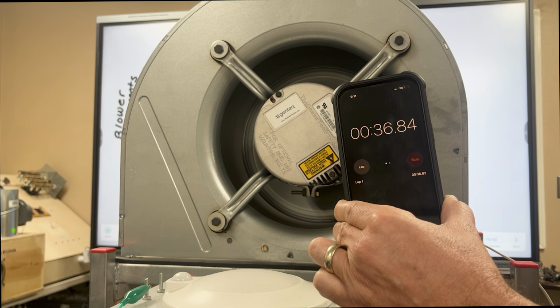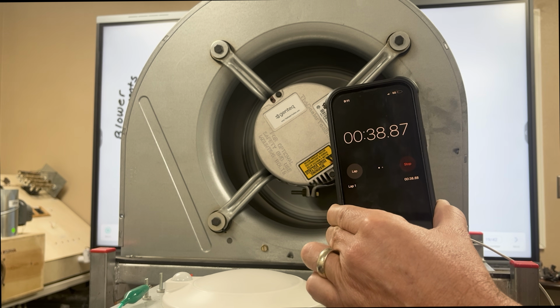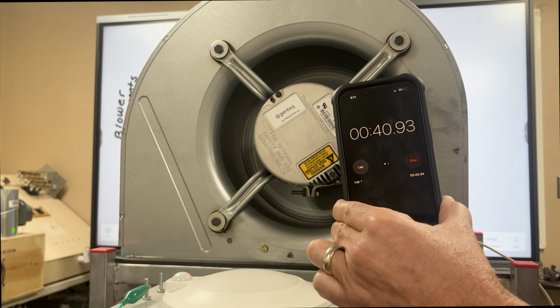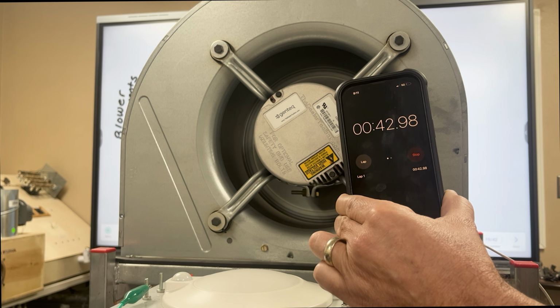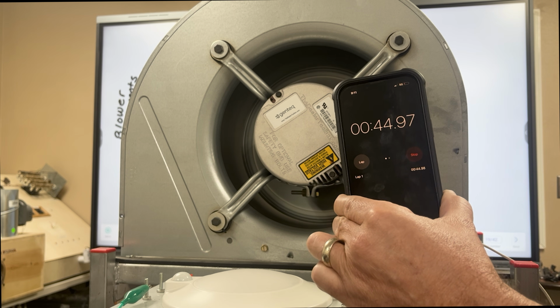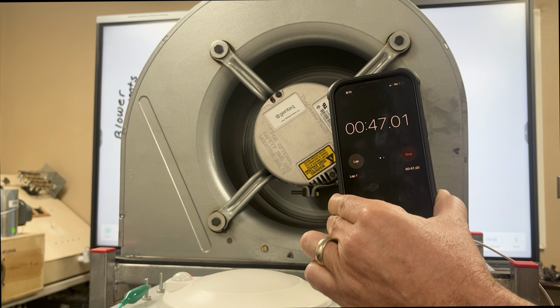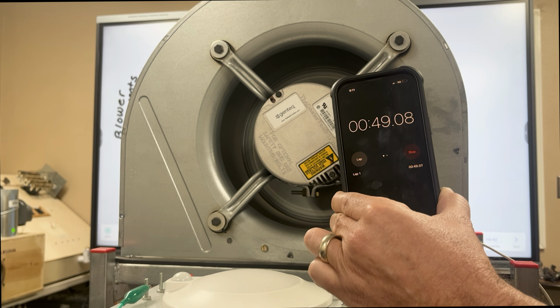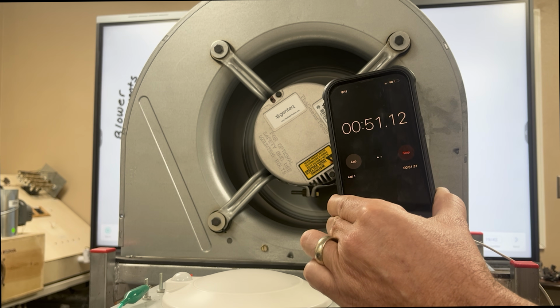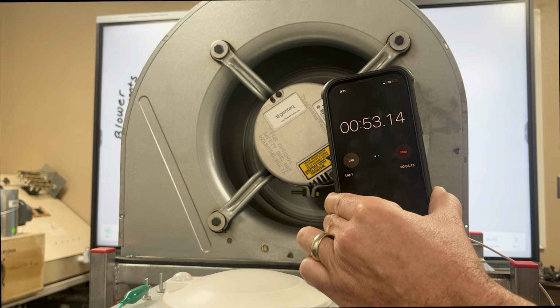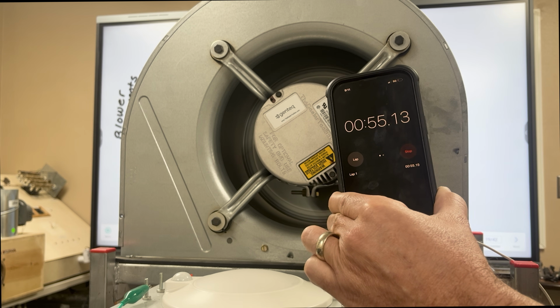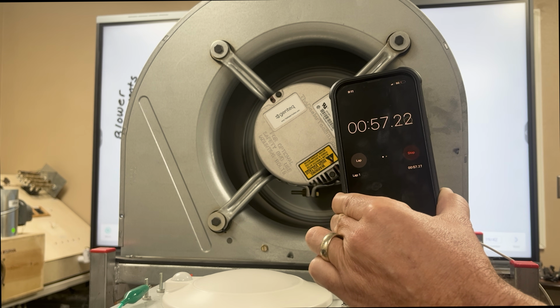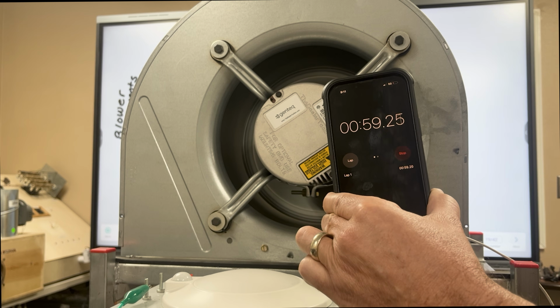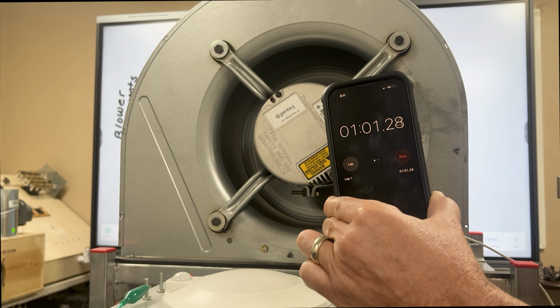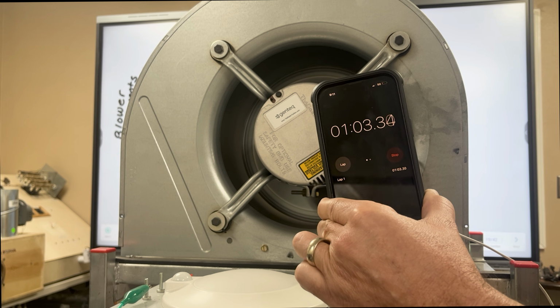So when you're diagnosing these, you want to be patient. And as I always say, use a timer. Most cell phones have that little stopwatch there. And we're getting pretty close to a minute and 30 seconds or 90 seconds. And this motor is pretty consistent. I've tested it several times in our lab, so it should cycle off in about another 29 seconds here.